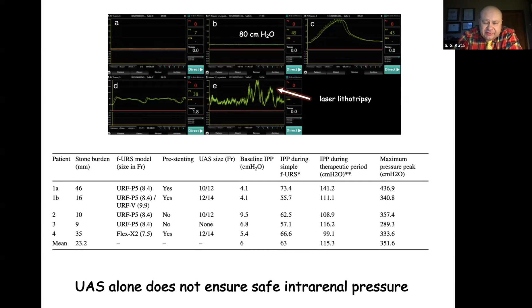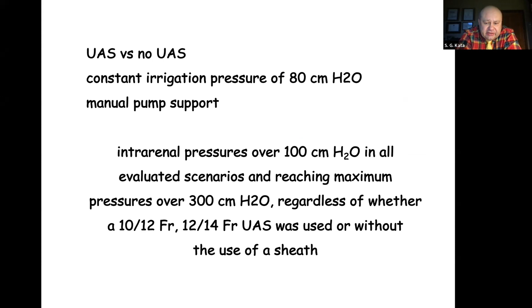What's very scary is, as you can see, regardless of whether we've got an access sheath or not, and whether we've got a bigger or smaller access sheath, maximum pressure peaks are very high. It's over 300 or even reaching 400 centimeters of water column. So from that study, we can say, yes, our ureteroscopy can be a danger to the pelvicaliceal system and kidney. A conclusion from that study was that whether we are using or not using an access sheath, when we are using manual pump support, pressure goes very high regardless of the access sheath.